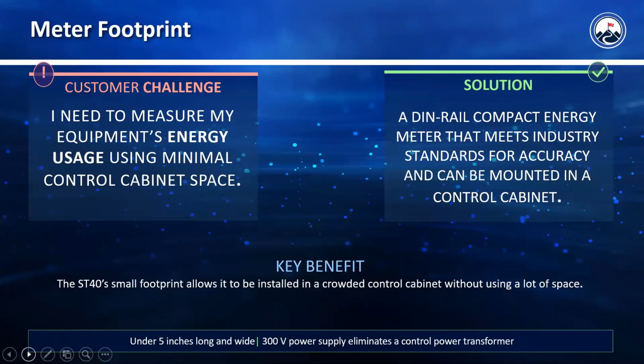So one key benefit of the ST40 is the meter's footprint. If you're facing a challenge where you want to measure your equipment's energy usage, but your control cabinet space is very small, you can DIN rail mount this, and this meets all of the industry standards for accuracy. You can mount it in there. The small footprint will help you install it even into a crowded cabinet without using a lot of space. In terms of size, this is under 5 inches long and wide. Also, it comes with a 300-volt power supply, so you do not need an additional control power transformer. Again, you will be saving space on that.